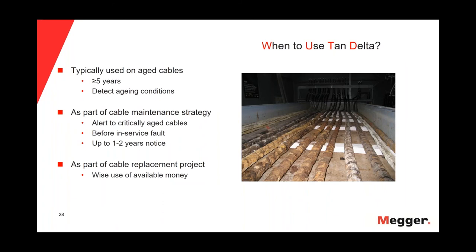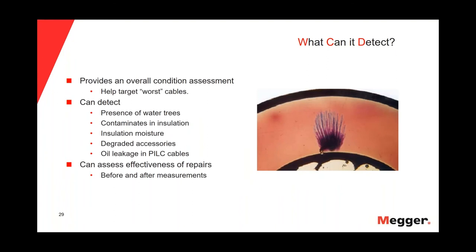When to use the tan delta? We use it typically on aged cables — at least cables that have been in service five or more years. The goal is to detect aging conditions in the insulation. We can use the tan delta as part of a cable maintenance strategy to alert critical aged cables before an in-service fault, providing up to one or two years' notice. We can also use it as part of a cable replacement project. What can we detect? The tan delta provides an overall condition assessment of the cable insulation — it helps us target the worst cables. We can detect the presence of water trees, contaminants in the insulation, insulation moisture, degraded accessories, and oil leakage in paper-insulated cables. We can also assess the effectiveness of repair.